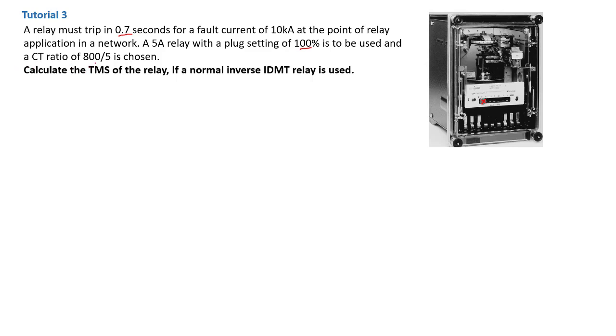Moving back to this tutorial: the CT ratio chosen is 800 over 5. They are asking us to calculate the TMS — the Time Multiplier Settings of the relay — given that a normal inverse IDMT relay is used.